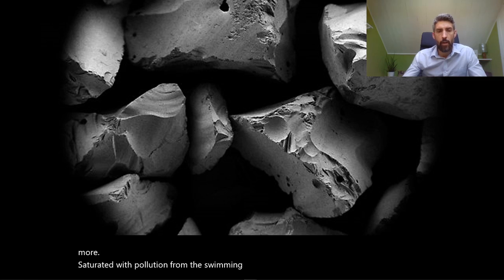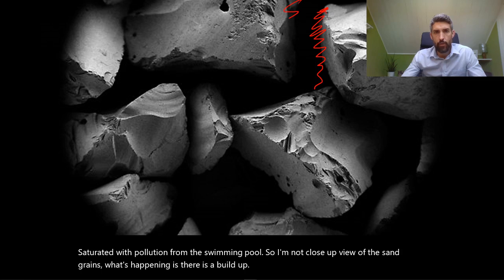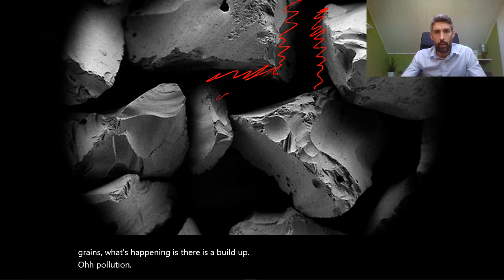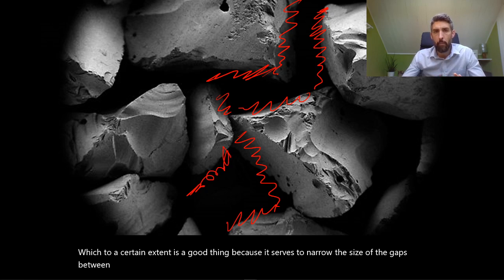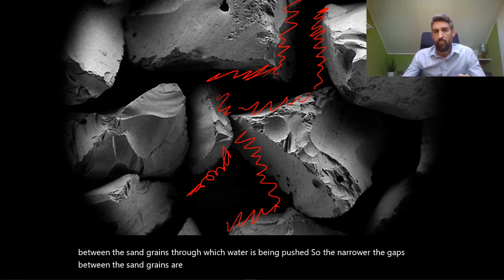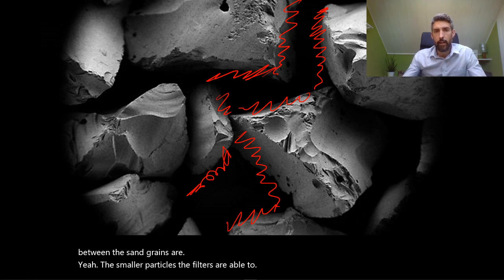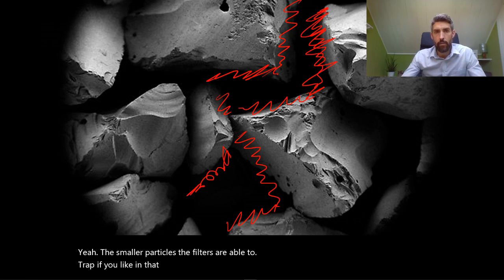On a close-up view of the sand grains, what's happening is there is a build-up of pollution happening, which to a certain extent is a good thing because it serves to narrow the size of the gaps between the sand grains through which water is being pushed. So the narrower the gaps between the sand grains are, the smaller particles the filters are able to trap.